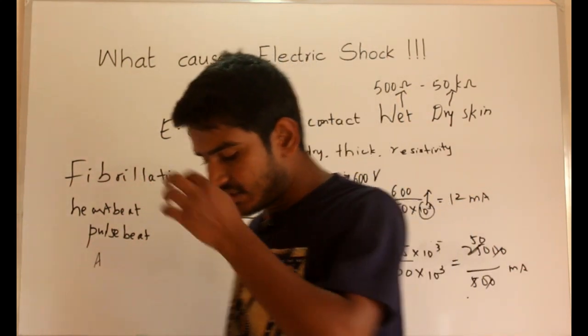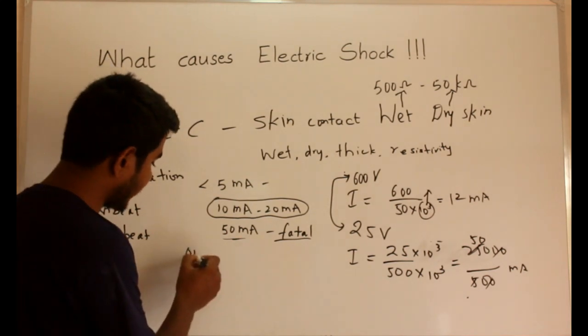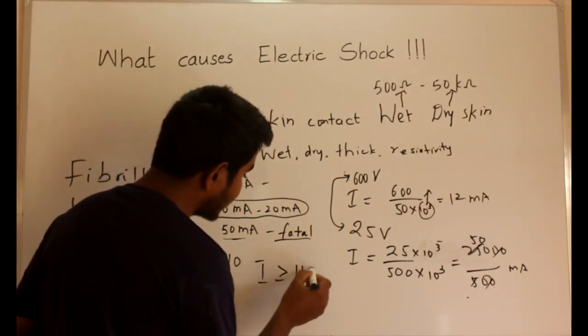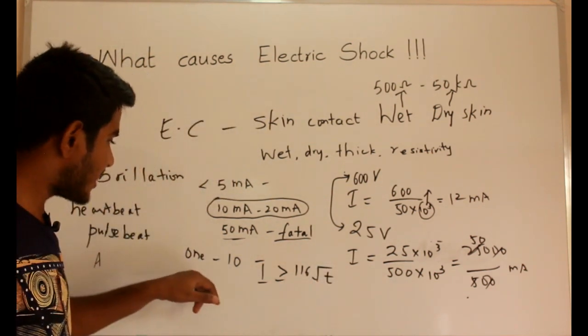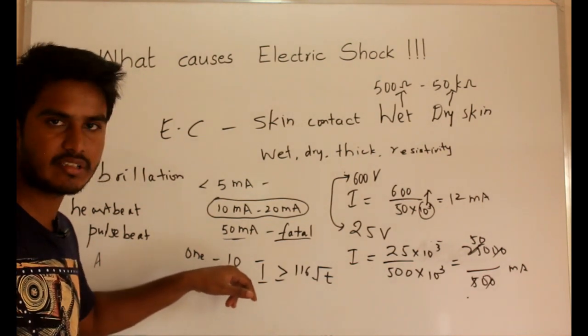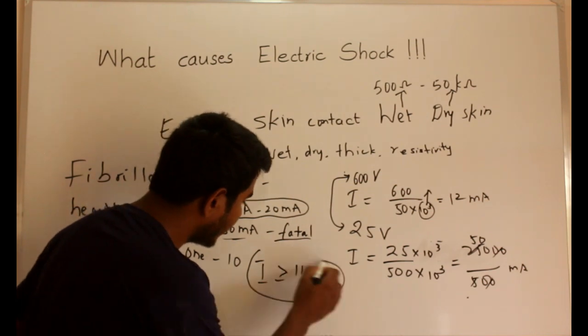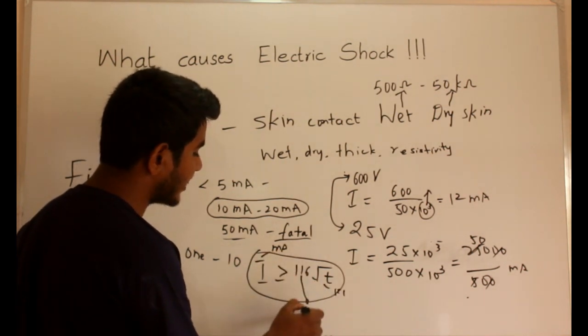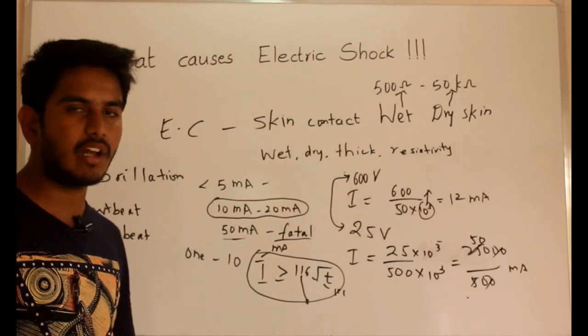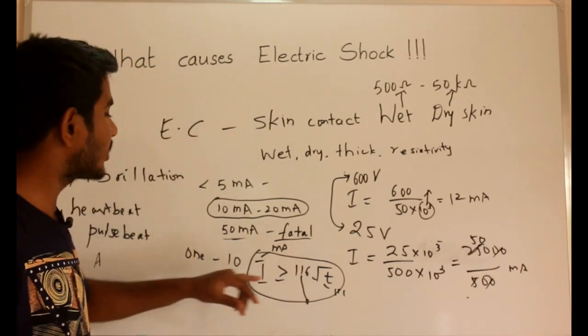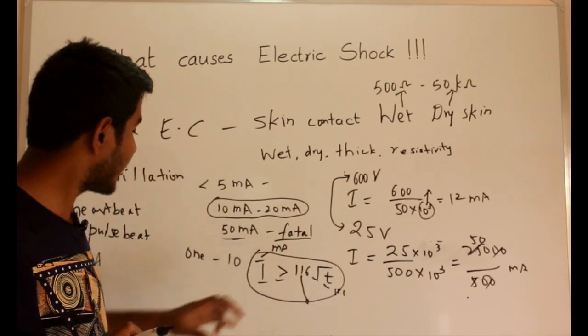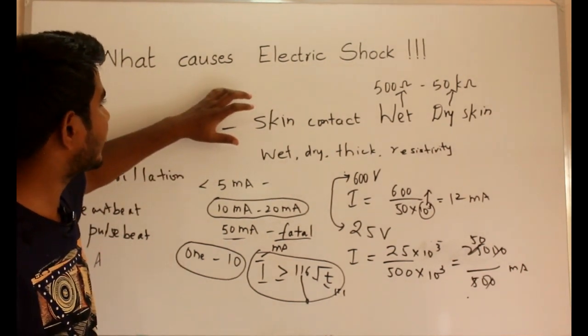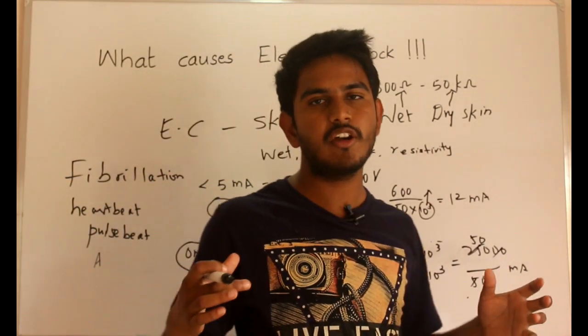Statistical investigations have also shown that there is a one-in-ten chance of death if the current satisfies the equation: I ≥ 116 / √t, where I is in milliamperes and t is in seconds, and 116 is an empirical constant expressing the probability of a fatal outcome. You can use this equation to assess whether a current level is potentially lethal. This is all about what causes electric shock — I hope you understood well, thank you.